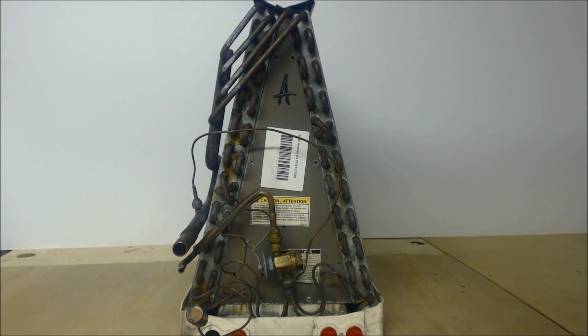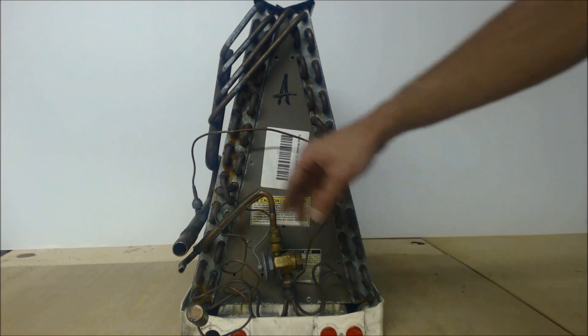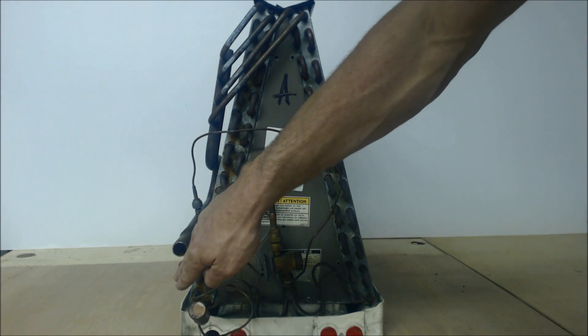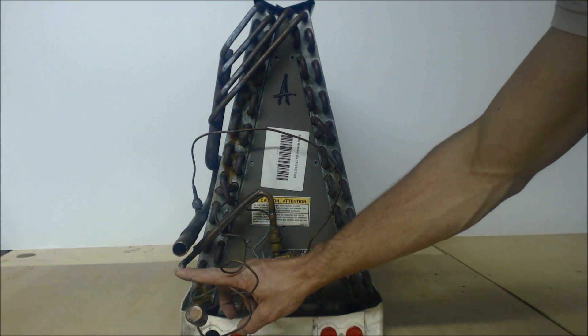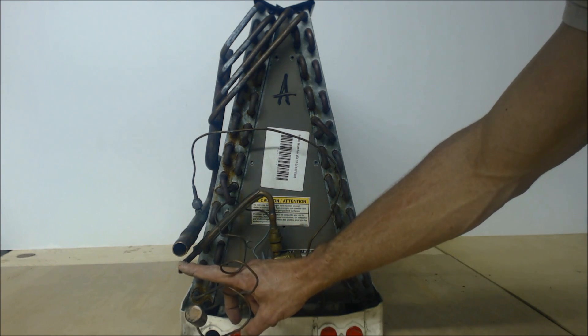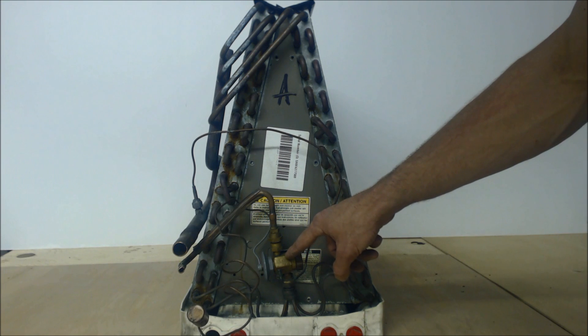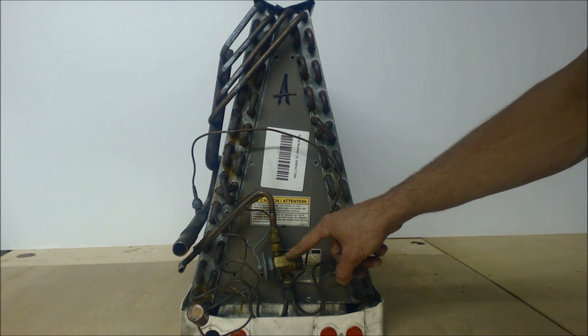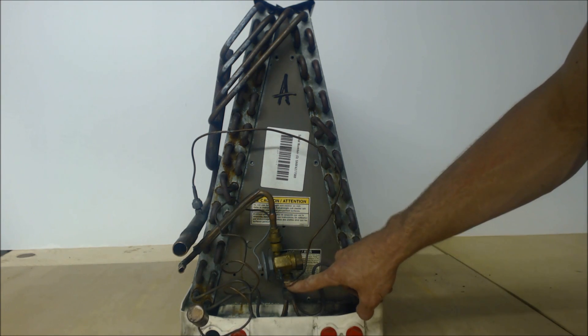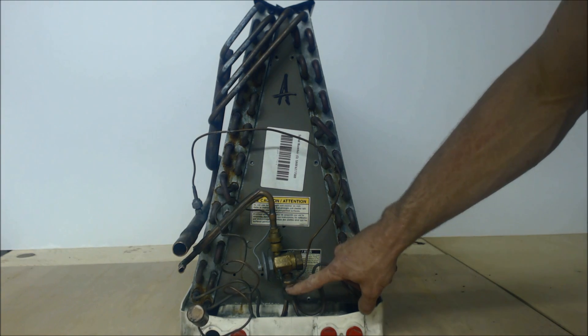So how this thing works: you have your suction line and your liquid line. Your liquid line comes in with high pressure, high temperature liquid refrigerant, hits the metering device - in this case a thermostatic expansion valve - and turns into 20% flash gas and 80% liquid.